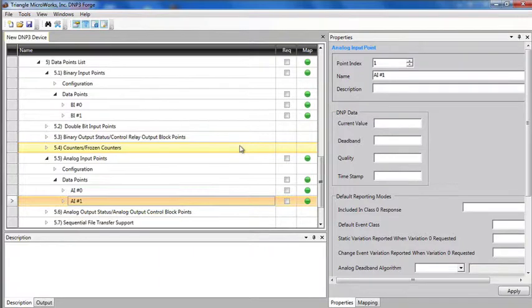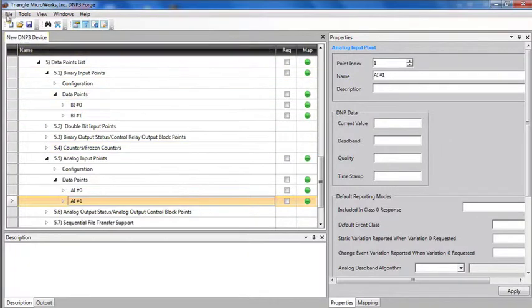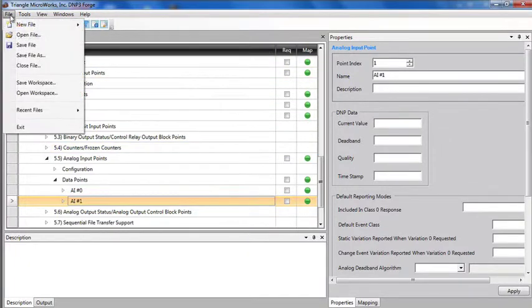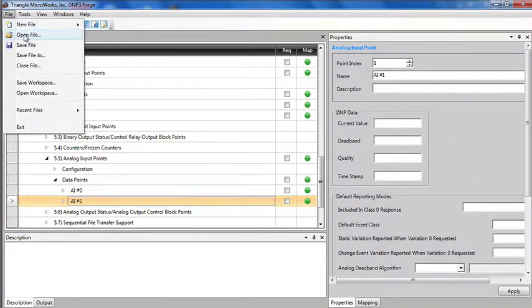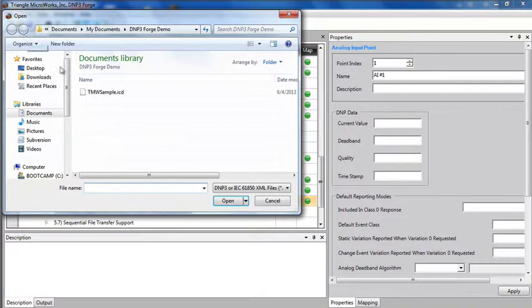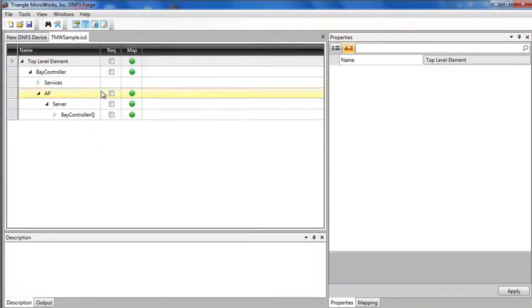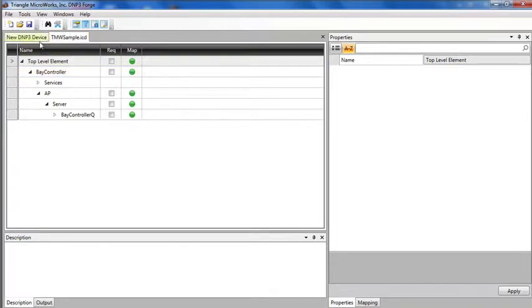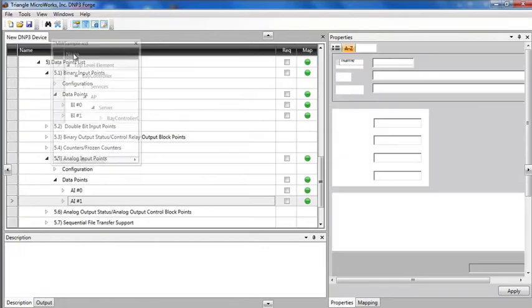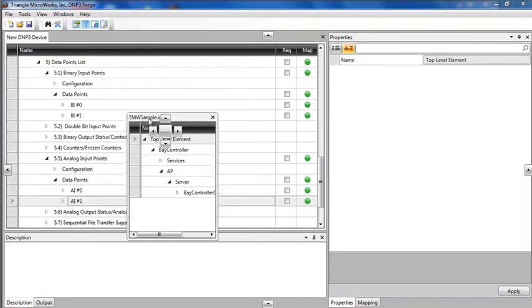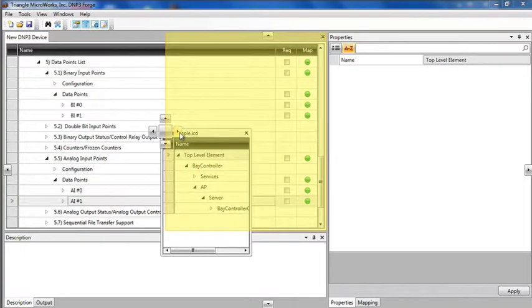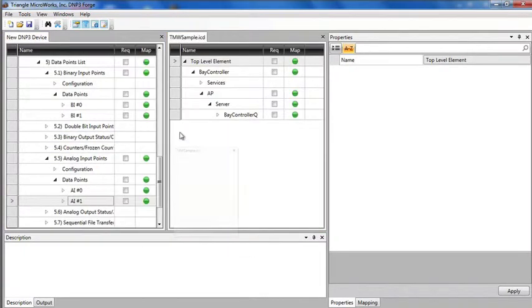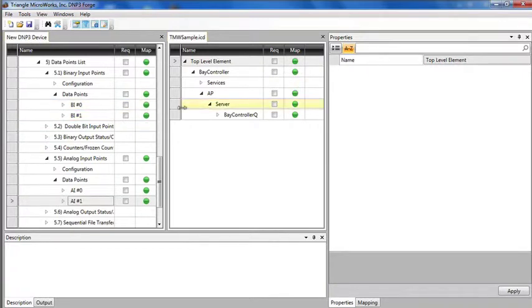Now let's take a look at how we can map between 61850 and DNP3. To do that, I'll open an ICD file. I say file, open file, and load my ICD file. Mapping is easily accomplished by drag and drop, but that's easier if I can see both my ICD file and the device profile at the same time. I can grab the ICD file and rearrange my display so that the DNP device profile and the ICD file are side by side.